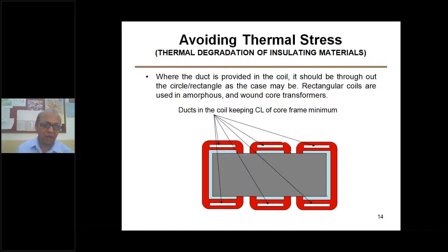Then come to the mechanical properties of the conductor, which is very important, and which I am emphasizing again and again. See what are the things: contact resistance, contact force, which is very important, seed defect, some defect we have provided in the design or manufacturing, and that cannot be removed, that will cause the failure, oxidation, metal creep, heating, cleaning, crimping, tightening, sharp bends. This is also important. Sharp bend causes fatigue. Vibrations, shrinkage of insulation and board during service, and these are important mechanical parameters, out of which metal fatigue, elasticity of metal, metal creep, they are very important things to be considered.